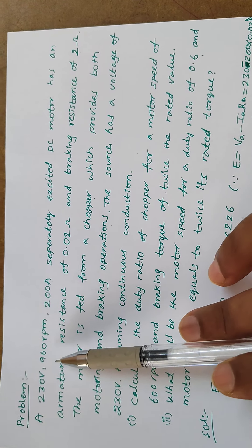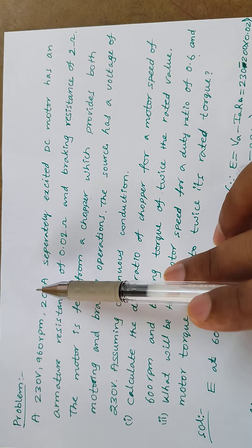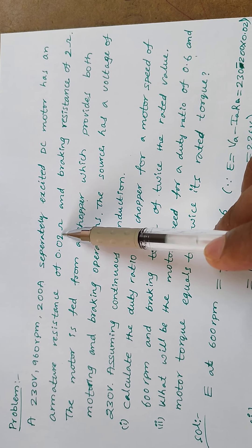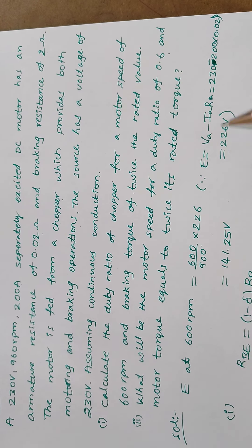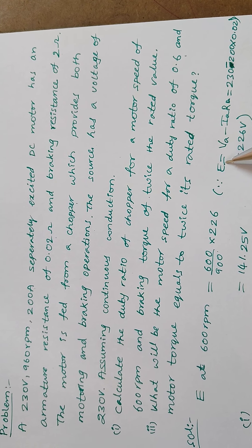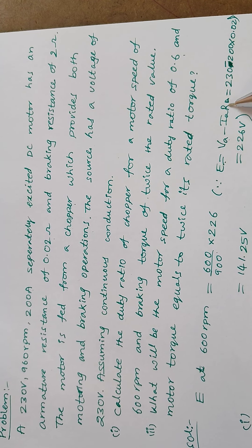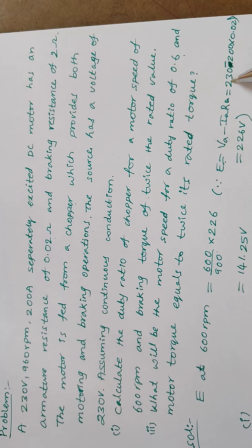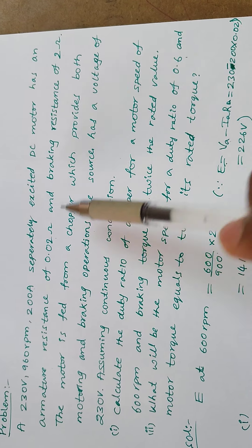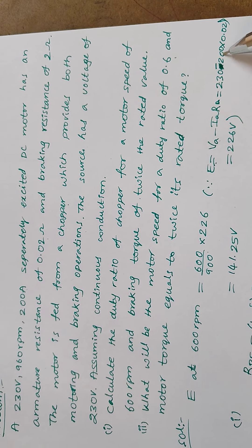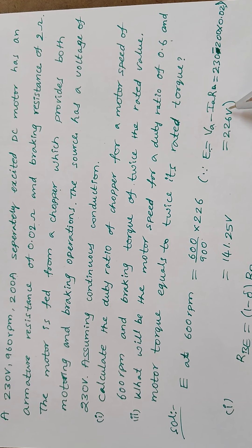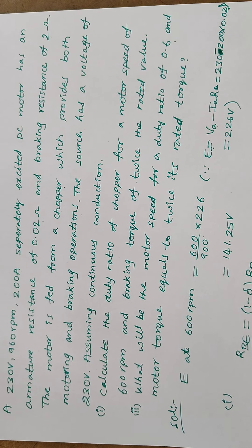From the given data: 230 volts, 200 ampere, armature resistance 0.02 ohms. We'll find out the rated back EMF first. Rated back EMF is Va minus Ia times Ra, that is 230 minus 200 times 0.02, which gives 226 volts as the rated back EMF.